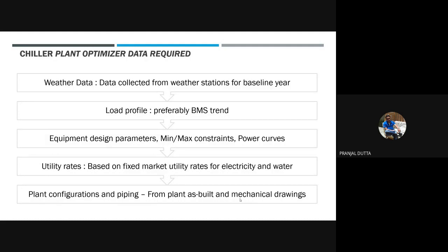Then we need to collect all the design data for chillers, pumps, cooling towers, all equipment. And we even need all the control logics. Let's say in a particular plant there are 10 chillers: how are these 10 chillers prioritized, meaning which chiller is number one, number two, number three. When load goes up, accordingly the number of chillers turned on increases, and when load goes down, the low priority chillers will be turned off. So we need all the control logic for the entire plant.